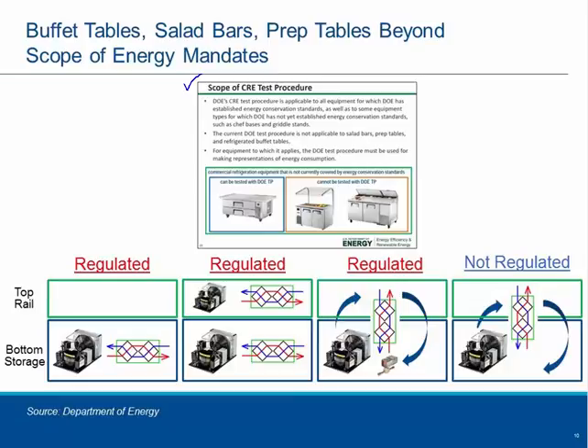Therefore, this system is, in fact, regulated. Then you go to the next one, where if you have some kind of cooling capacity and a heat exchanger on your top rail that is independent and separate from the bottom storage area, this could almost be considered as an open display case that has a DOE test procedure, therefore that can be tested. And then this bottom one as well, it would be classified as an undercounter.